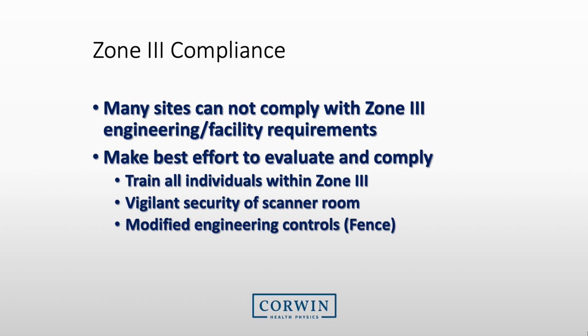Many MRI sites are old, and they were configured before many of these safety regulations were created, so compliance with Zone 3 is very difficult. We would typically like to have Zone 3 separated and access controlled by badge or code, but this is sometimes not possible. For these sites that struggle with engineering controls for Zone 3, we recommend that you make your best effort to evaluate and comply with Zone 3 requirements. Ensure that all individuals are trained within Zone 3. Maintain vigilant security of the scanner room. Also, consider some modified engineering controls, such as ferromagnetic monitors or plastic fences, to prevent individuals accessing Zone 4.